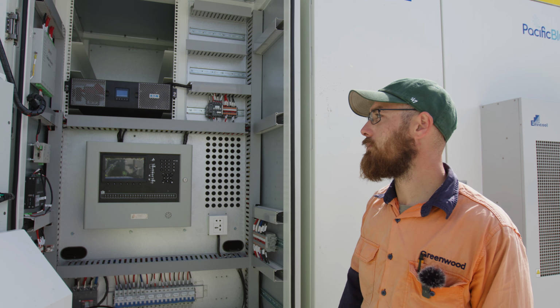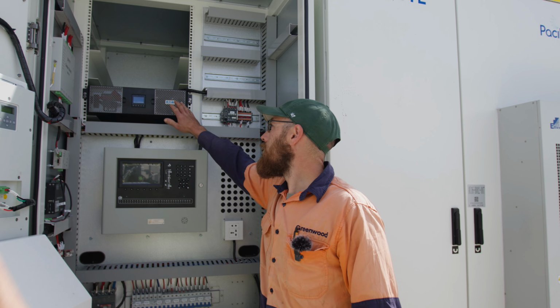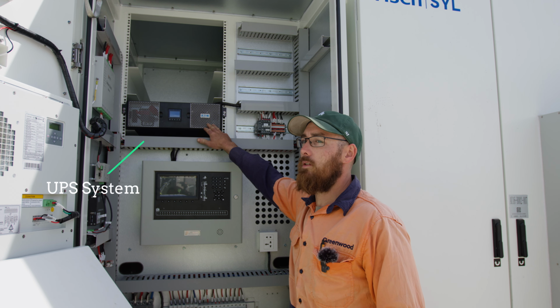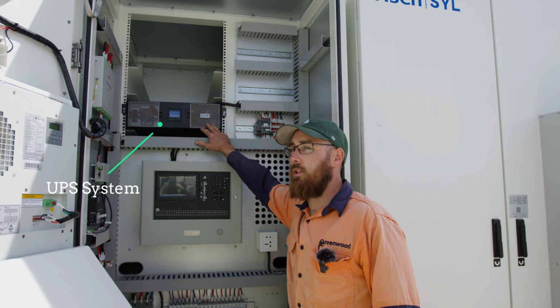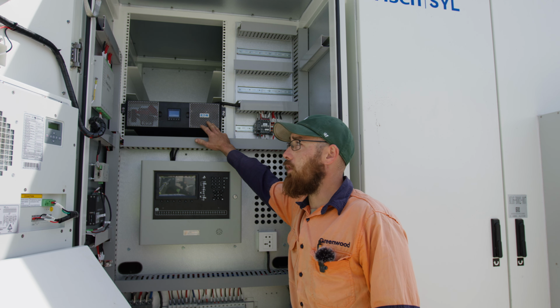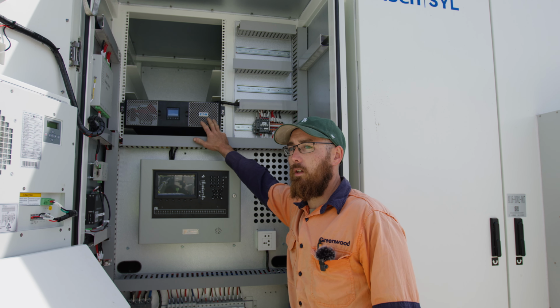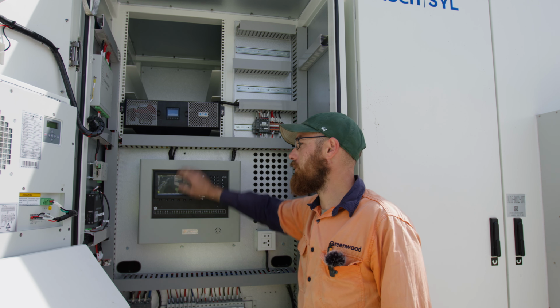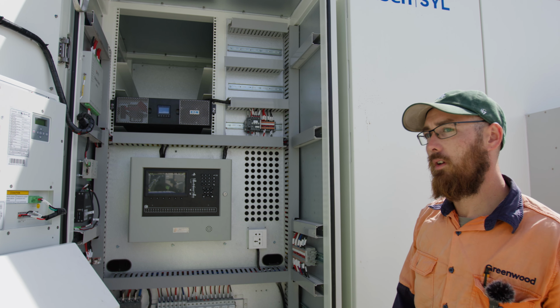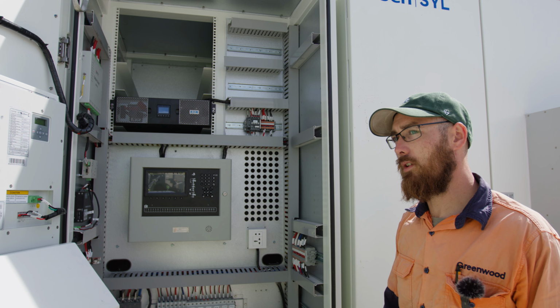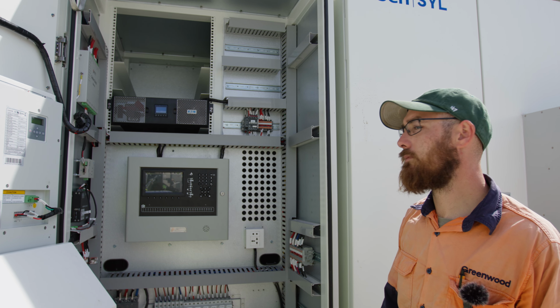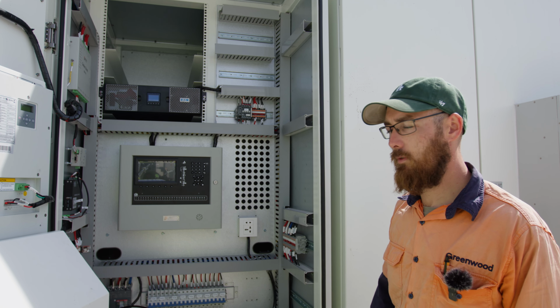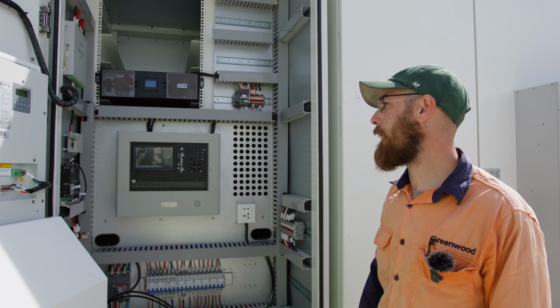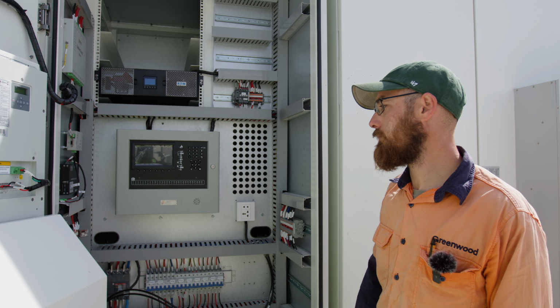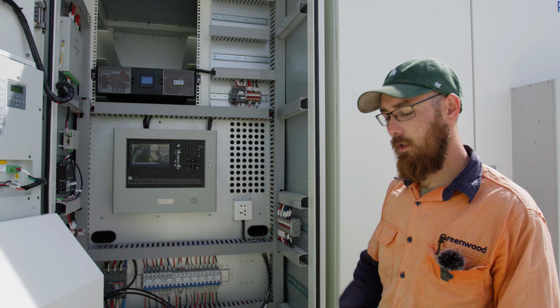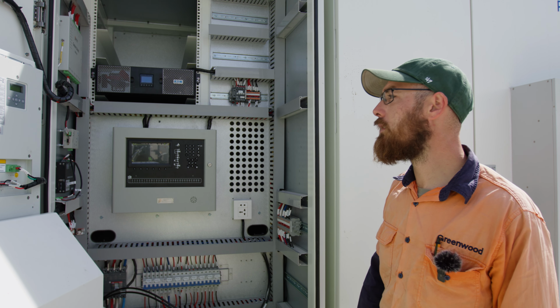Right, interesting. Now, this box over here, you mentioned... This is a UPS system, which will keep the controls for the BESS and the inverters all in operation if there was a power outage at all times, so they can safely shut down or just see what's going on site. And obviously when power resumes, the UPS gets charged back up automatically. And I'd assume they're using a lithium iron phosphate battery or something similar within the UPS. Yeah, a bit of lithium battery.